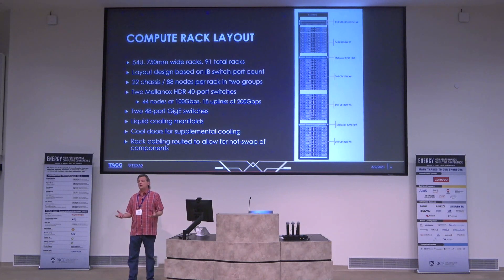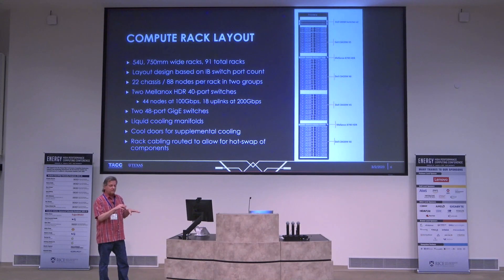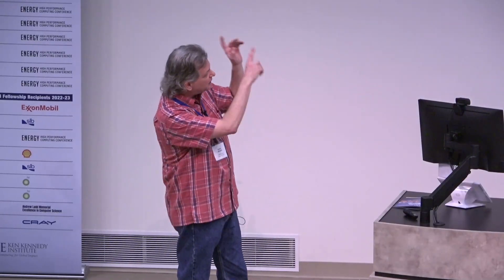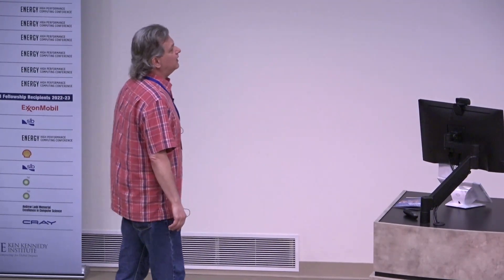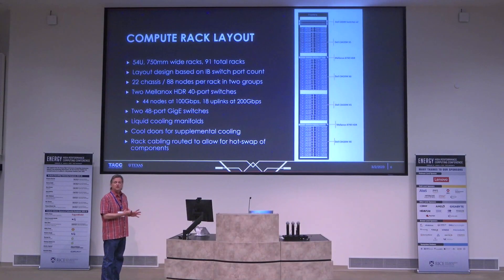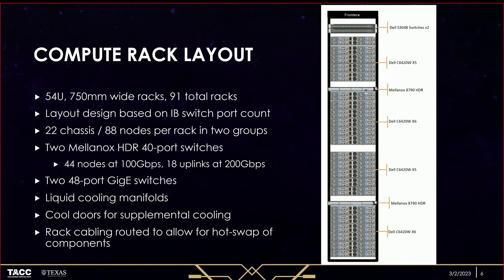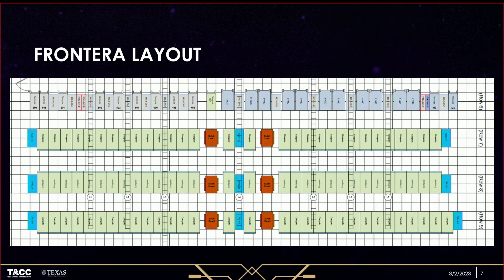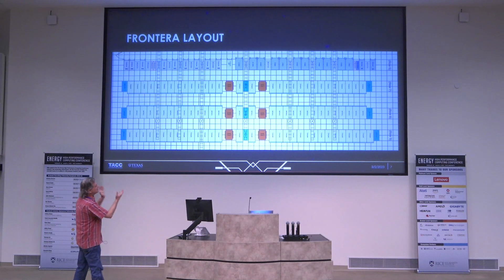It's important that we be able to work on the hardware — all nodes are rear-accessible. We have to be able to pull nodes out with all the liquid cooling manifolds, power distribution, InfiniBand, and gigabit cabling in the rack. We worked with Dell to design and lay out the racks so we can still pull out all the hardware and work on it. We do our own hardware repairs at TACC. And by the way, that's true of every system — DIMMs fail, and you're going to have to replace them over time no matter what vendors say.